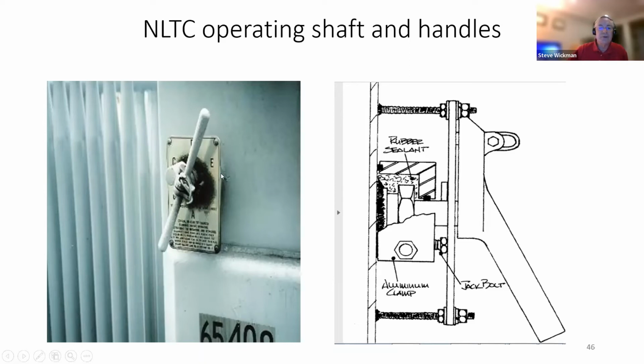Now, in those situations where you don't have a faceplate of this nature, we have made just a clamp that would go over the entire no-load tap mechanism handle and cap on the outside. In a case where it isn't going to have as big a handle on it here, that would effectively contain the leaks. And in that situation, if you do need to go back and change your no-load tap, we can come out, take that clamp off, allow you to change that no-load tap, put it on the position you want it. We'll reinstall the clamp and refill it with sealant compound for it.